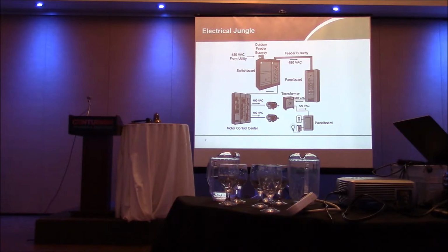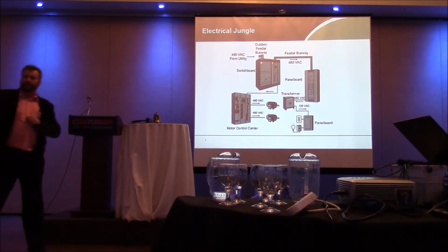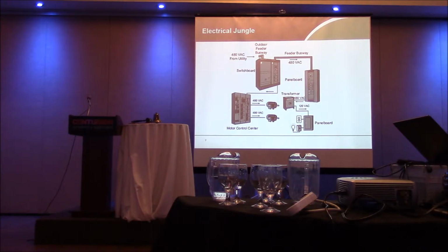If my motor control center is set up for 600 amps, and this is a true story, if my motor control center is set up for 600 amps, and you come back to me and say, yeah Jeff, sorry, but we're going to be bigger than that -- if that's already on site, you can't retrofit it, you can't add another conductor inside of it. You're buying a new one. So you're tearing the old MCC out, putting the new MCC in. It's taking you 12 weeks to get the new MCC, and he's billing you for a new MCC and for disposing of the old one. You might be able to get rid of it with a small, say, 25% restocking charge. New conductors to feed it. Oh, and yeah, delay claim.